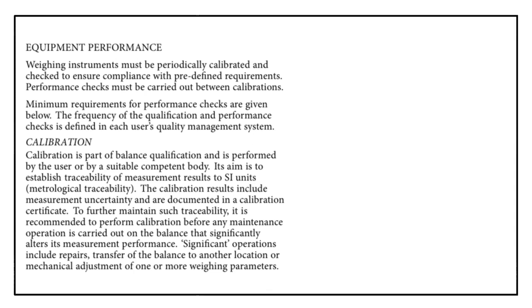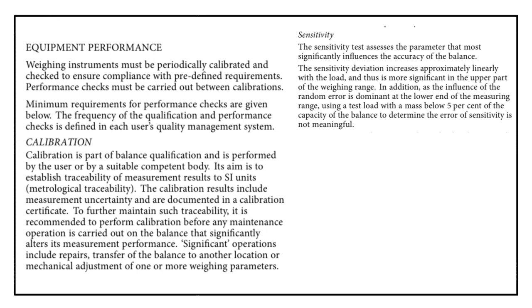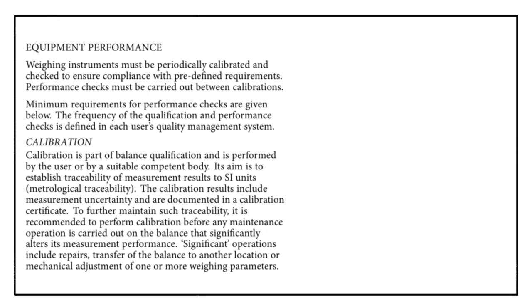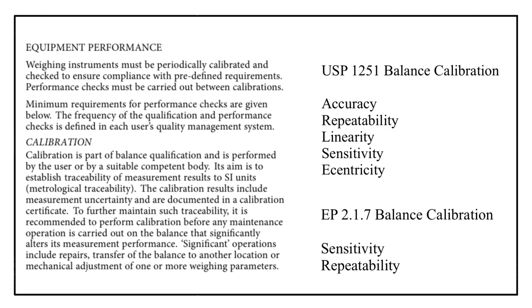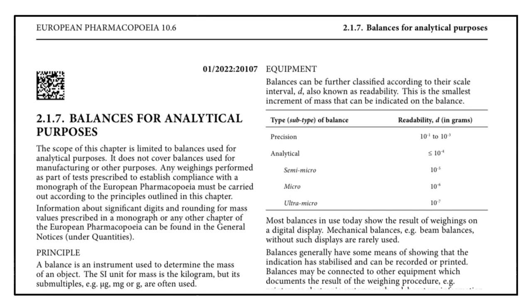As per EP chapter 2.1.7, there are two test parameters for balance calibration: sensitivity and repeatability. In contrast, USP specifies five balance calibration parameters: accuracy, repeatability, linearity, sensitivity, and eccentricity. This highlights a key difference between EP and USP general chapters with respect to balance calibration requirements.